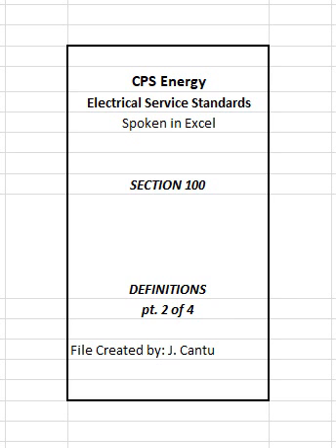A conductor used to connect equipment or the grounded circuit of a wiring system to grounding electrode or electrodes. Grounding electrode. A conducting object through which a direct connection to earth is established. Grounding electrode conductor. A conductor used to connect the system grounded conductor or the equipment to a grounding electrode or to a point on the grounding electrode system.